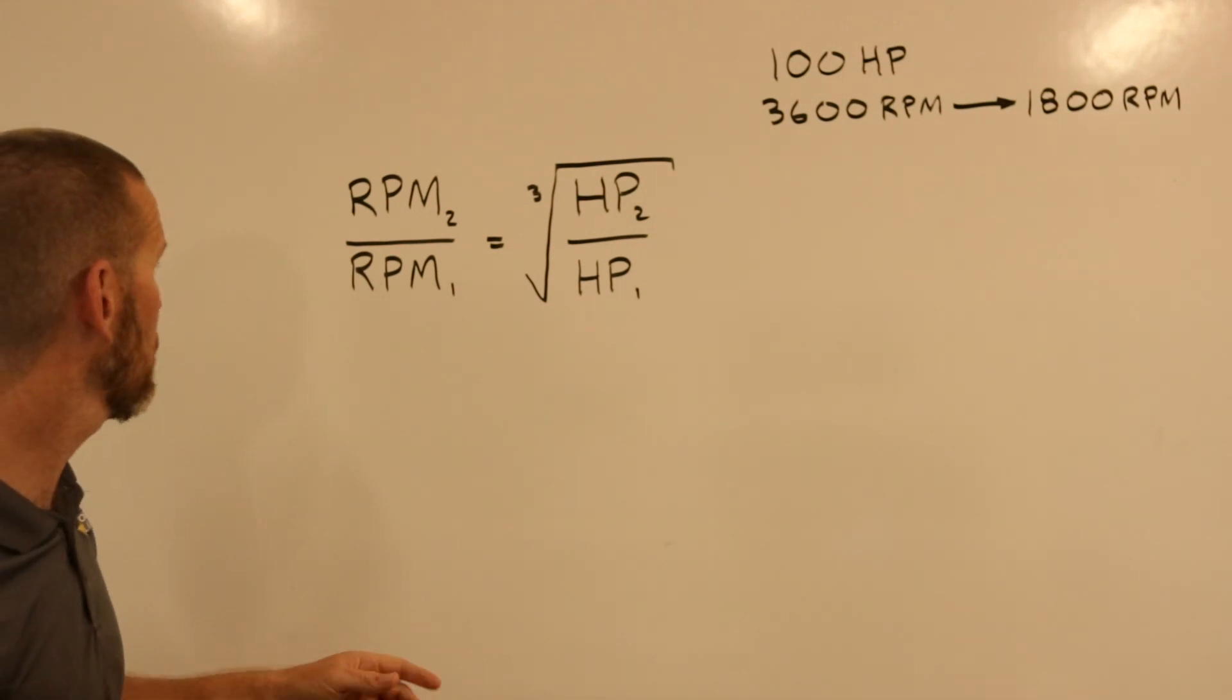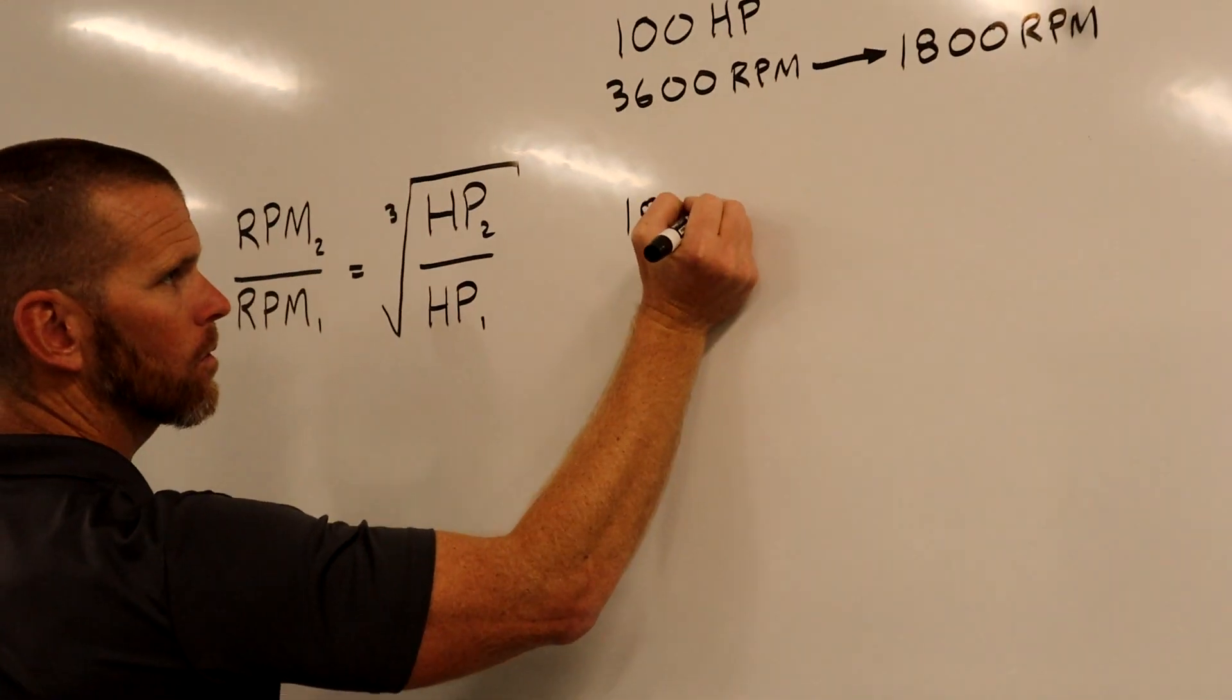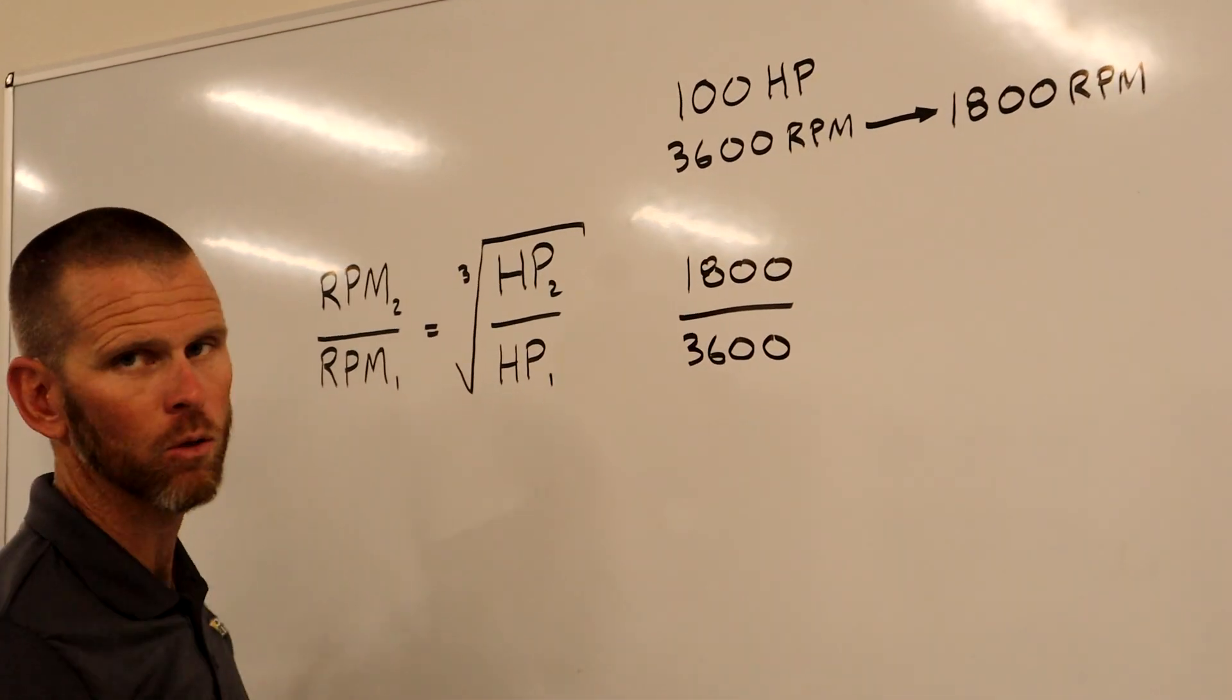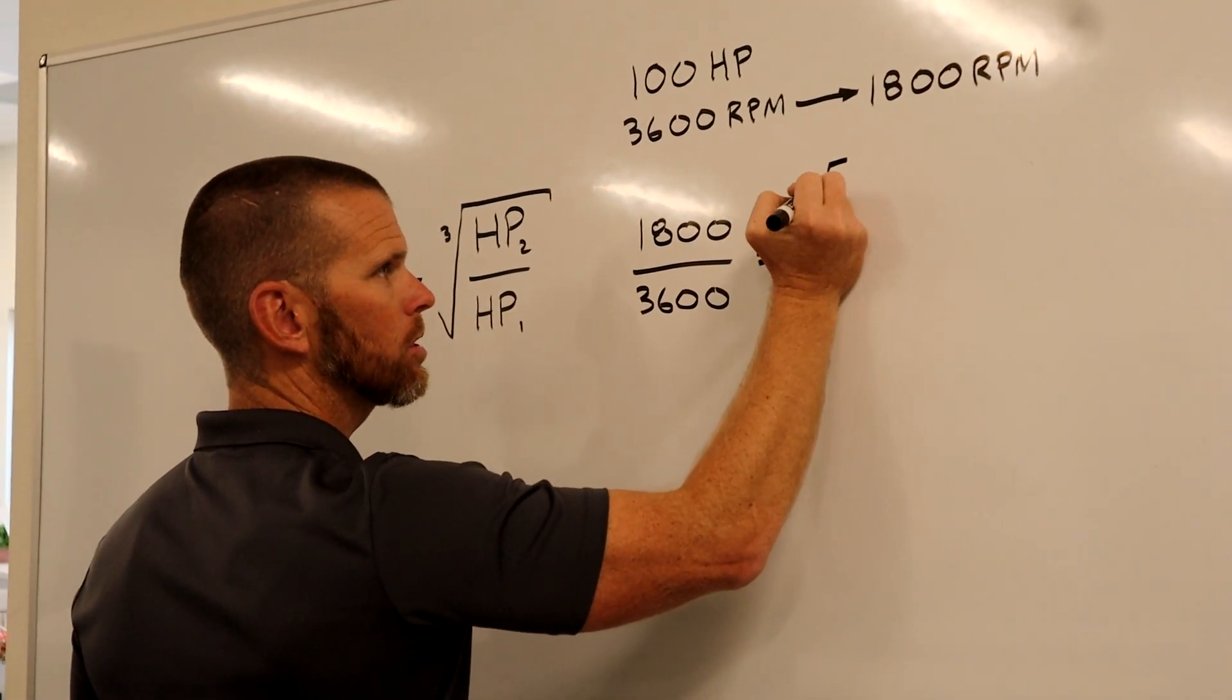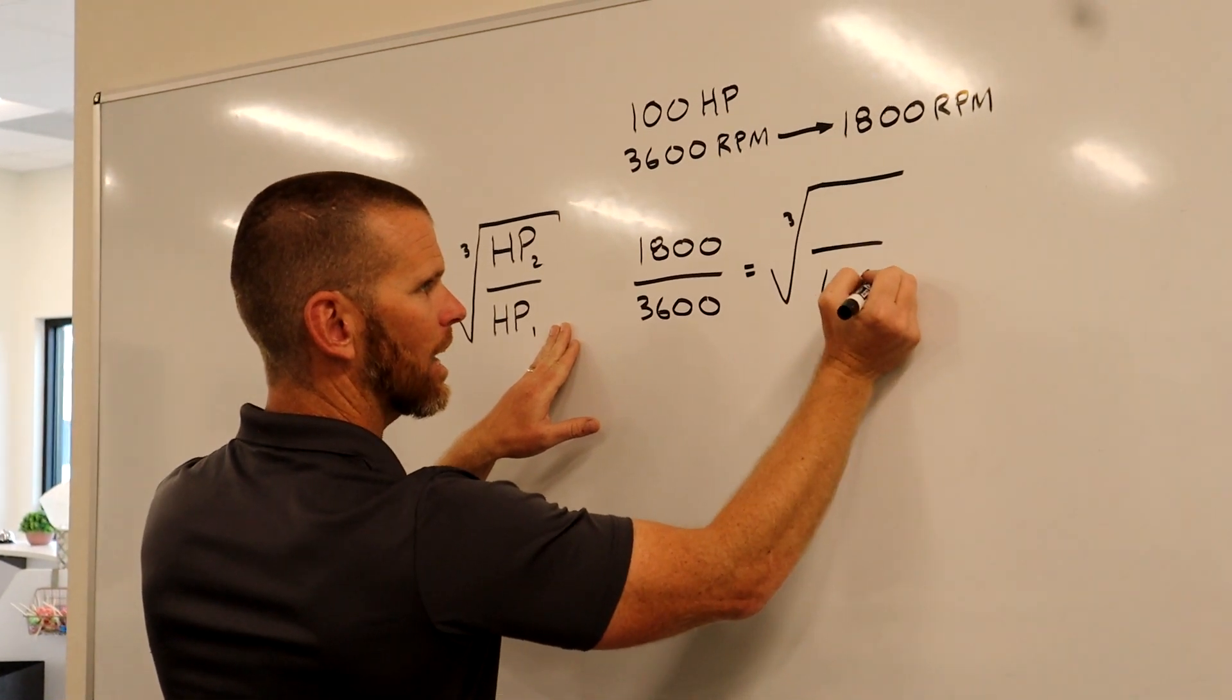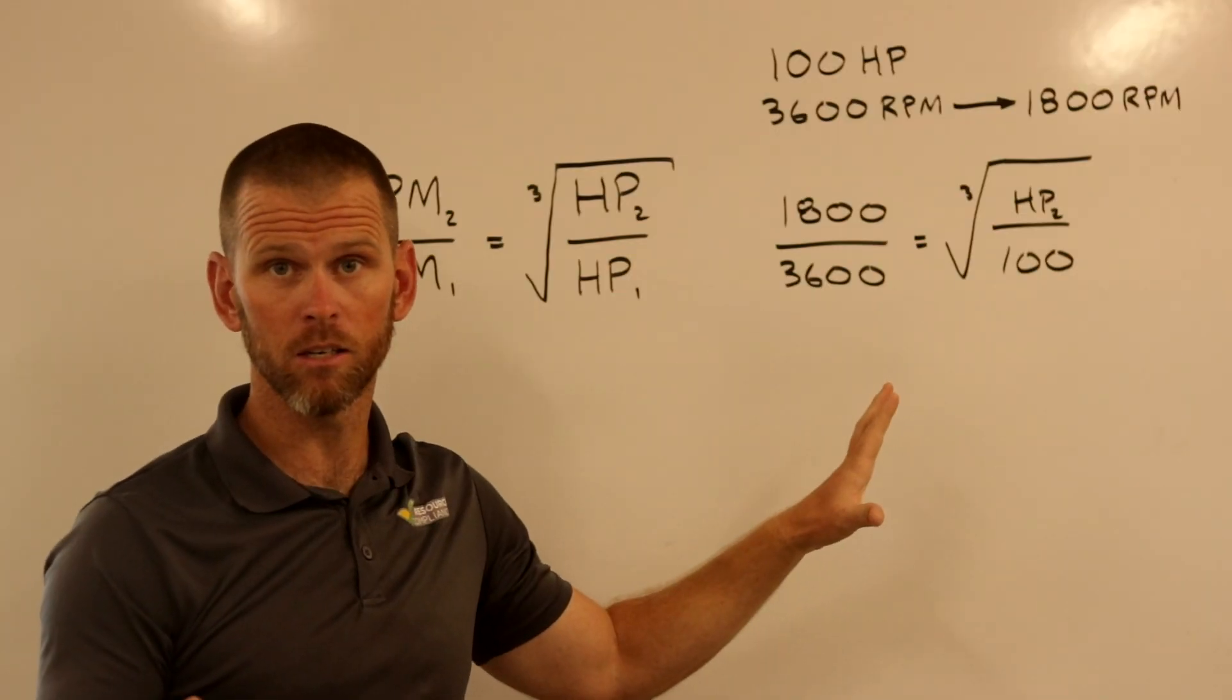We have our second RPM on the numerator, our first RPM on the denominator. These could be flipped. We can put the first up top and the second down low, so long as we do it on both sides in the same way. So let's go ahead and solve this problem. Our second RPM is given to us in the problem. It's 1800. And our first RPM, RPM one is 3600. Of course the units are RPM. They'll cancel out. And that's equal to the cube root of our horsepower at the beginning, which is a 100 horsepower compressor, and our horsepower at the end, which is horsepower two. That's what we don't know. Horsepower two is what we're wanting to solve. So we now have everything we need to solve this problem.